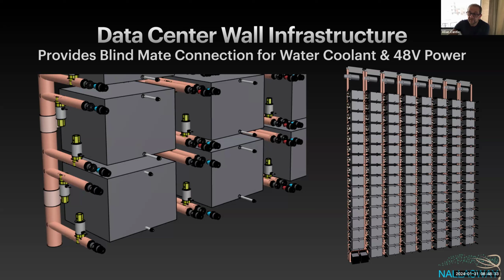But this is another piece. So in one column, if you're at about 1.5 kilowatts per module to 2 kilowatts per module, because you've got to cool the plugged-in media as well, then we're in the region of sort of 15 kilowatts per column. There's a heat exchange company that I met with at one of the OCP events, I think it was Prague, where it looks like a fairly small unit would do a 15 kilowatt heat exchange to the facility water.